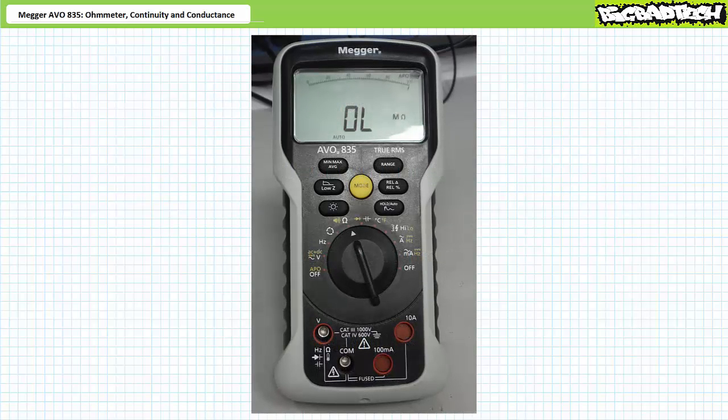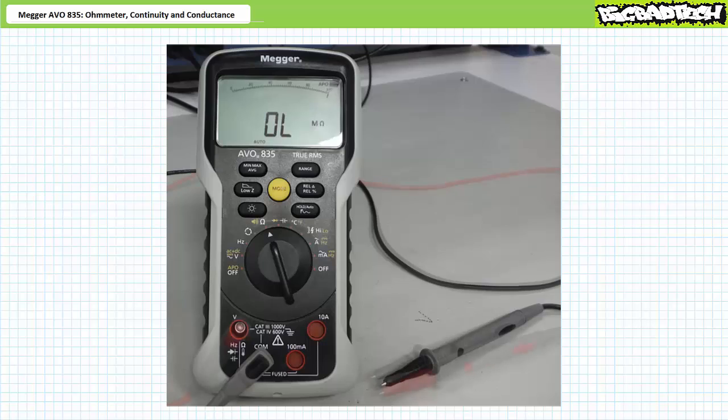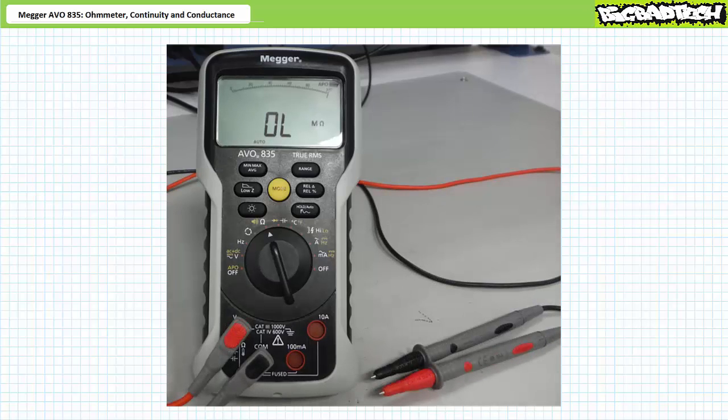To place the Megger AVO835 into ohmmeter mode, rotate the function dial to the selection with the ohm symbol. We'll explore other functions and the function buttons in later lectures. In this position, the AVO835 allows access to the black common terminal and the red live terminal on the left, identified with an ohm symbol. Black lead into the black hole, red lead into the red hole. The ohmmeter measures the resistance of an element in units of ohms placed between the two tips of the leads.